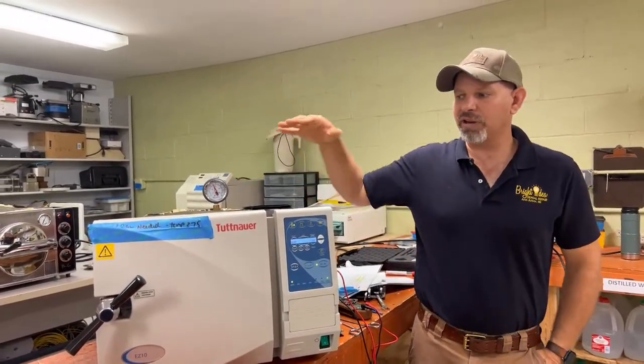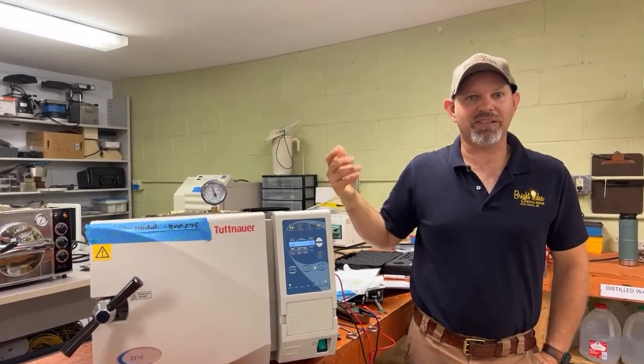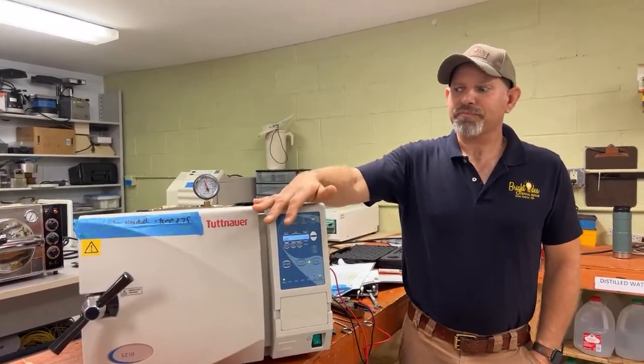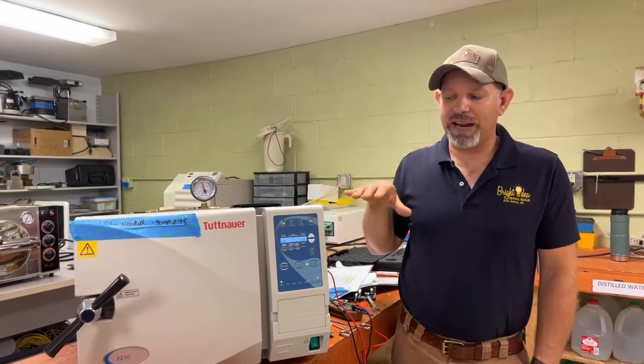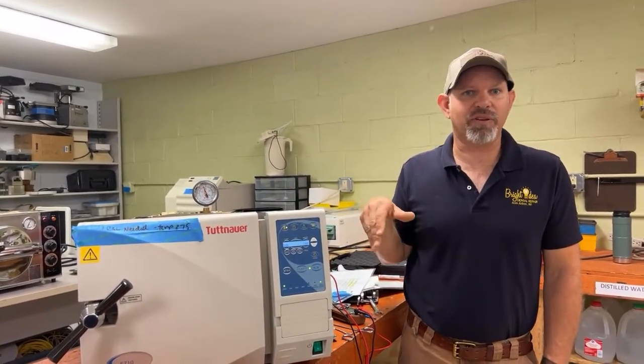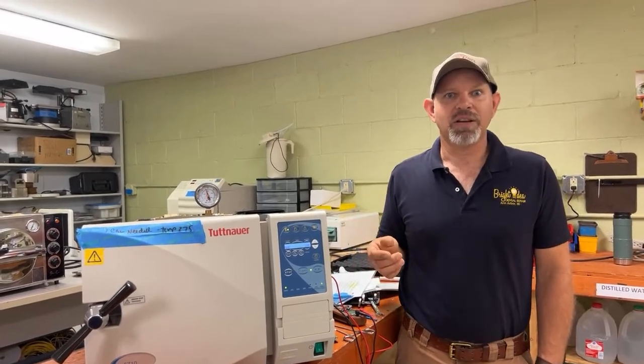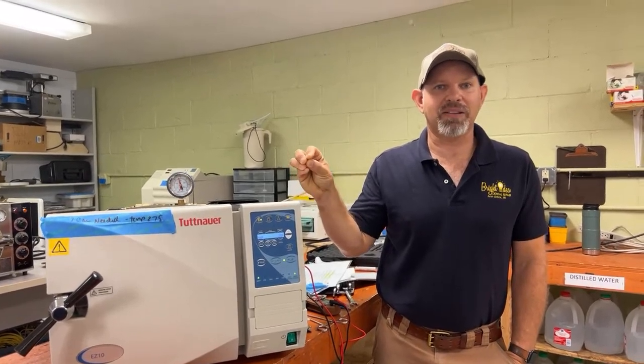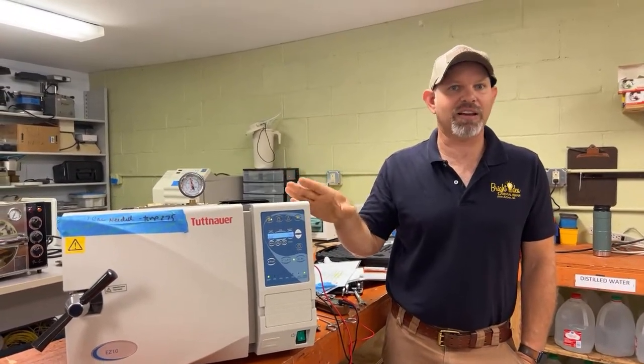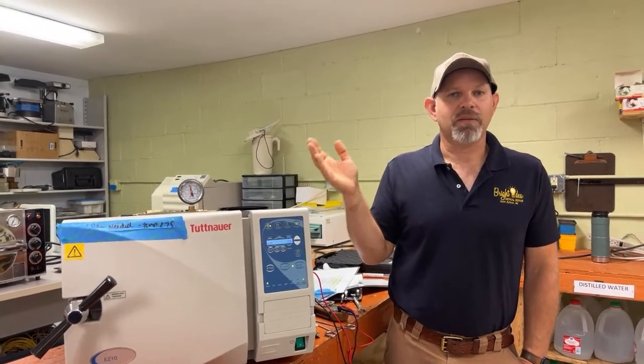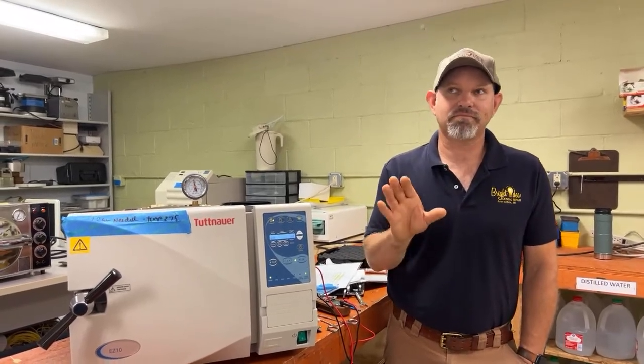Of course, that's a manual unit. With this one, the calibration is a place to start. The other thing that usually drives these calibrations is the fact that you have some sort of an error, some sort of a problem, it won't run. In dentistry, I will tell you, it's unfortunate, but it's true. Most offices are not really crazy about preventive maintenance. They won't do preventive maintenance just for the sake of it being the right thing to do. Just about everything with dentistry, in my opinion, is pain-based.